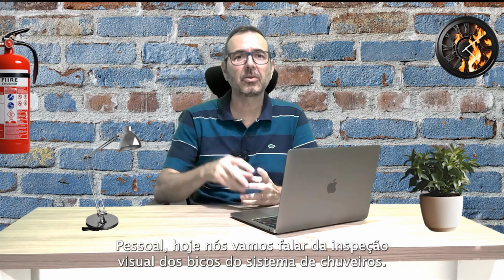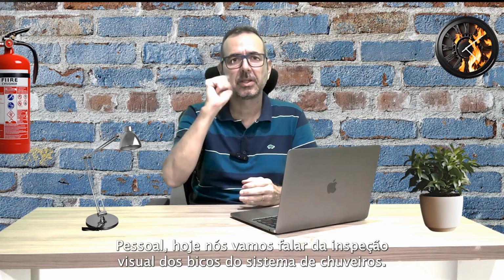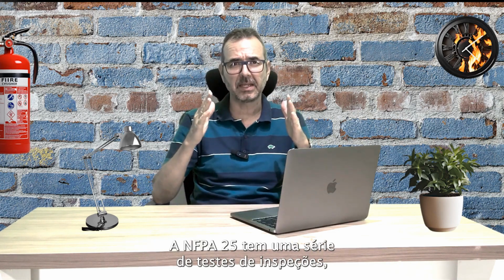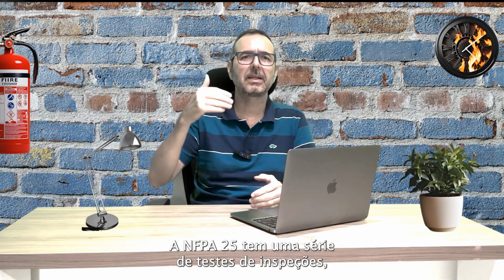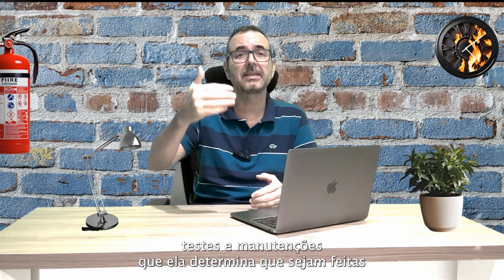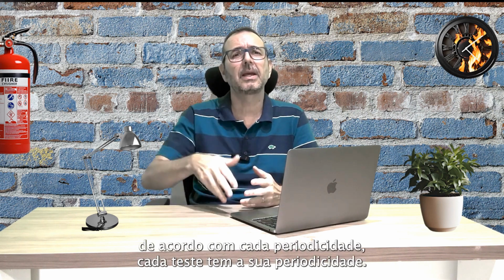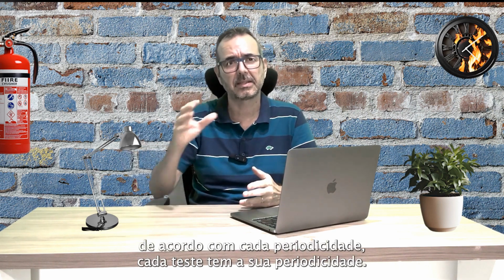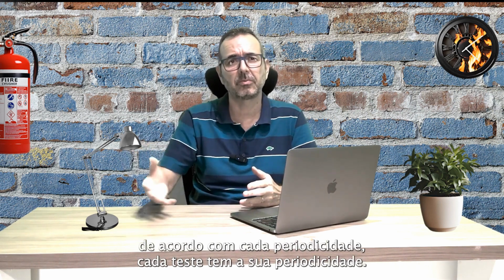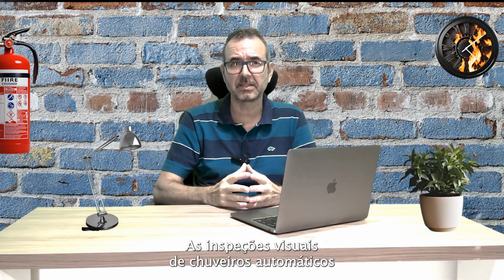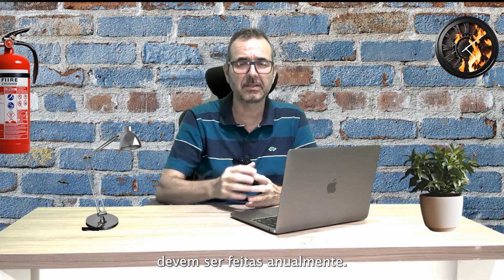Everyone, today we are going to talk about the visual inspection of the nozzles in the automatic sprinkler system. NFPA 25 has a series of inspection, testing, and maintenance requirements that it specifies to be performed according to their respective frequencies. Each test has its own frequency. Visual inspections of automatic sprinklers must be conducted annually.